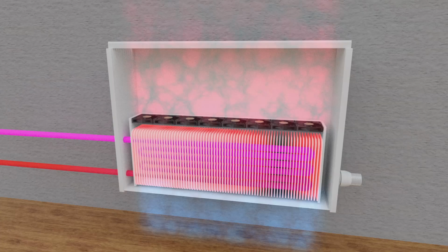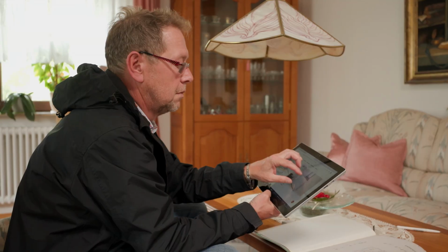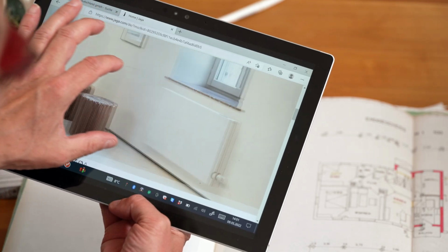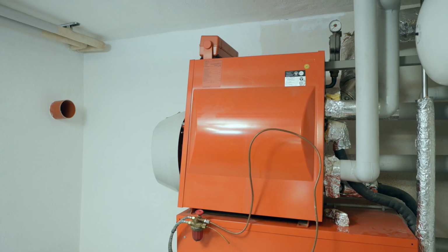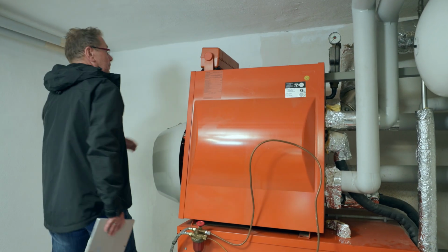In the case of the Rommels, the calculations show that the old radiators in the family house are large enough. When the radiators were installed 40 years ago, they were already thinking in large dimensions. We won't need to make any changes at all to the radiators. They're big enough for the heat pump and they should be able to work efficiently here. The old radiators can stay. This is often the case in many existing buildings. The old oil heating system, on the other hand, will have to go. Before that's done, though, it can still provide important information.